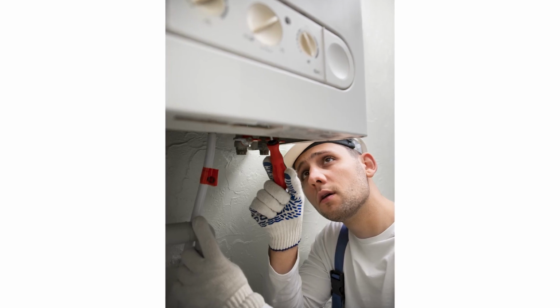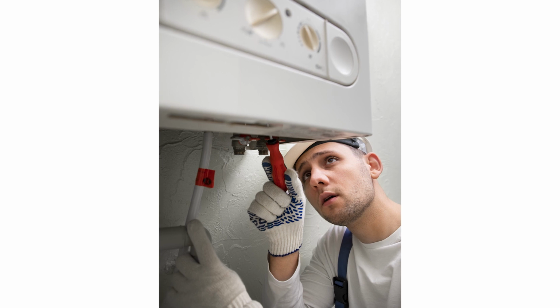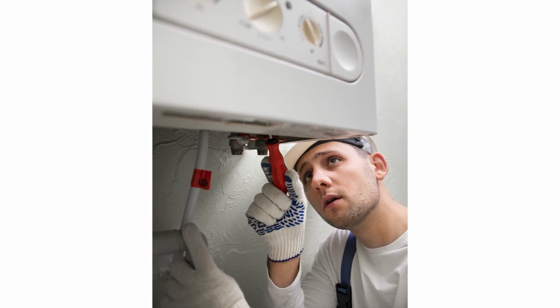Where an existing boiler has failed, the Daikin Altherma hybrid monobloc offers the opportunity for a heat pump system to be installed with minimal work to get heating and hot water restored quickly, with the ongoing benefits of a heat pump system. The Daikin Altherma hybrid monobloc system installation should take just 1 to 2 days for those properties where there is a short pipe route between the outdoor and the indoor unit, and no major changes are required to the rest of the heating system. Not only does this short time minimize disruption during the installation, it also keeps the total cost down.